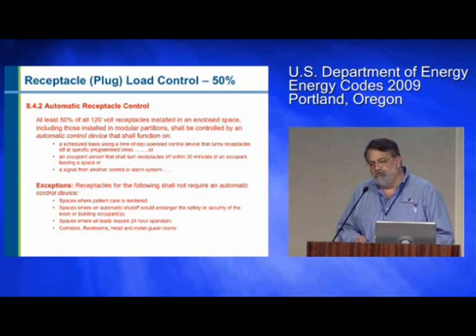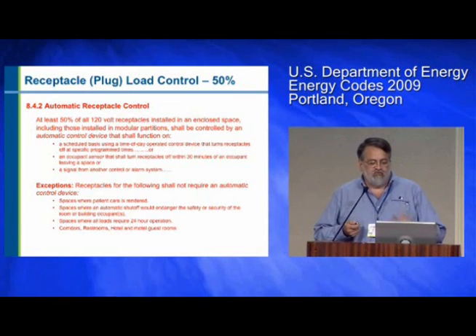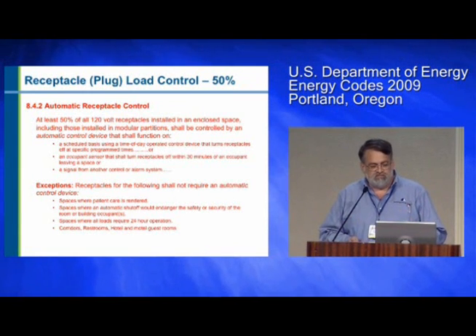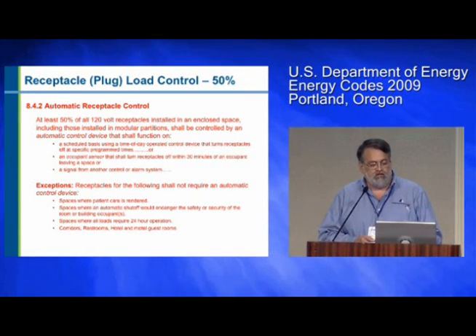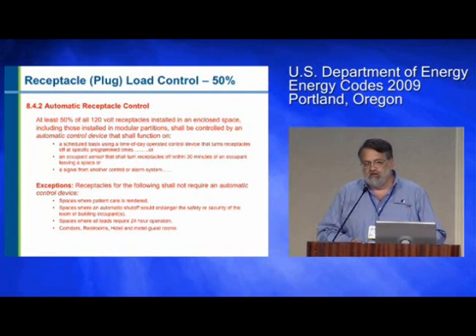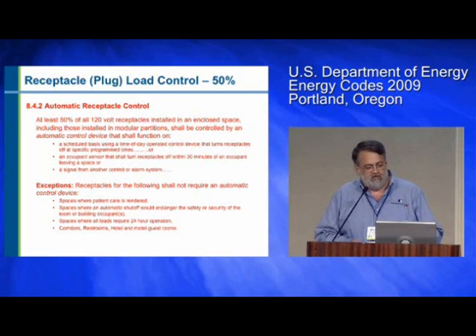Plug load or receptacle load control, I mentioned before. There's what we call a 50% requirement. It simply says you have to control at least 50% of your receptacles in an enclosed space, including those installed in partitions, with an automatic control device. And the automatic control device can be 3 basic types: either a scheduled basis, occupant sensor, or some other signal.